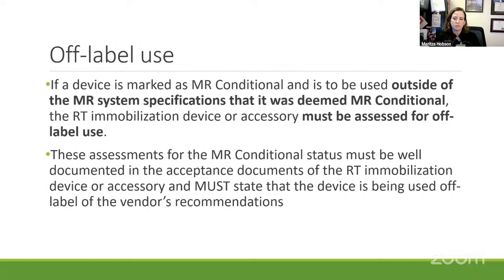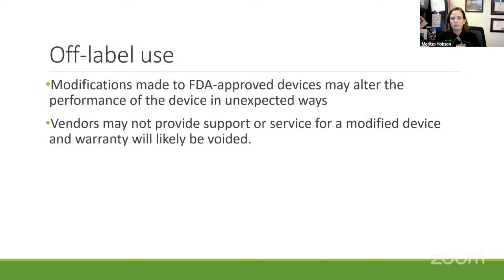So the assessments for MR conditional status must be well documented in the acceptance documents of the RT immobilization devices and must state that the device is being used off-label of the vendor's recommendations. Again, this is why it's important to know your system's values and stated in the table shown previously. So one thing to keep in mind, if you do these modifications to an FDA approved device, that may alter the performance of the device in unexpected ways, not just from the MR safety aspects, but also the mechanical aspects, right? So you need to be cognizant that the burden of liability lies with the user and your institution, and that vendors may not provide support or service for a modified device, and the warranty could be voided.